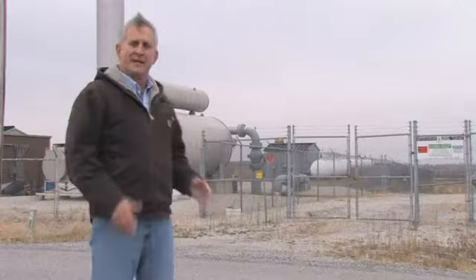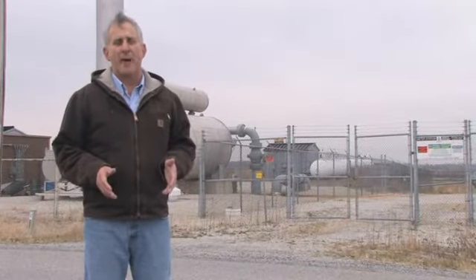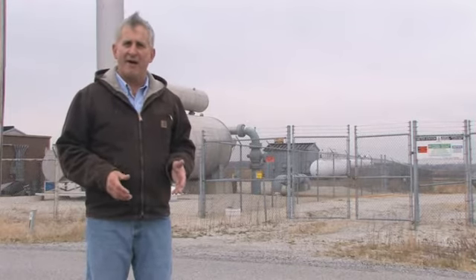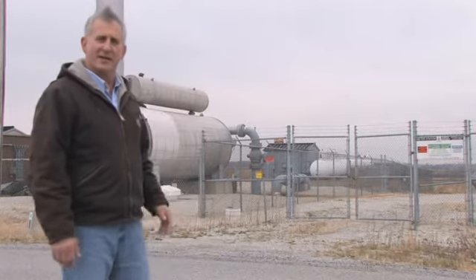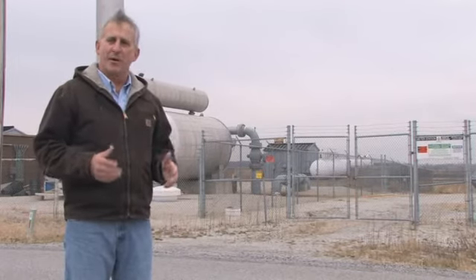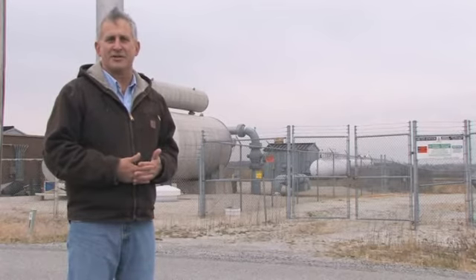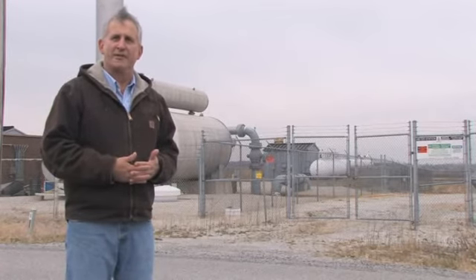A gate station, such as the one behind us, is a point where the distribution company takes natural gas from the pipeline company. Here, the natural gas is odorized, and that odorization becomes the customer's leak detector. Most people are capable of smelling natural gas odorant in a concentration in the parts per million range.